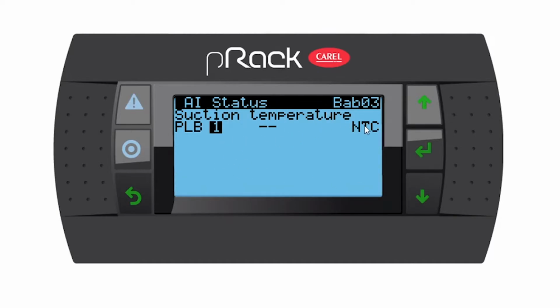So there's my upper value of 10, and my lower value, we're going to make it 0. Perfect. And we don't have a calibration. Perfect. If we go down, suction temperature, do we have one? Yes, we do. I'm going to assign it to U2, and it's a normal NTC as per the notes. Perfect. Let's go down. Condenser pressure probe. Yes, we do have one. I'll make it U3 for this exercise. 4 to 20 milliamp. Perfect. Upper value 30 bar and lower value 0 bar. Yes, that's perfect.